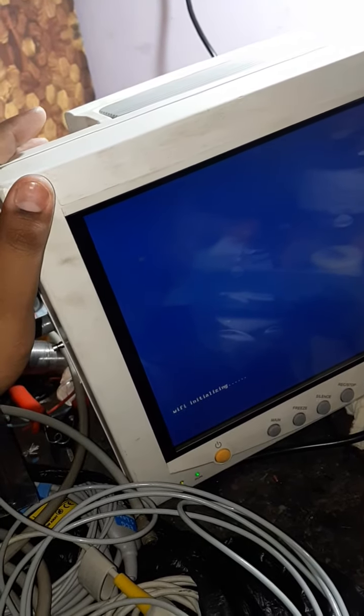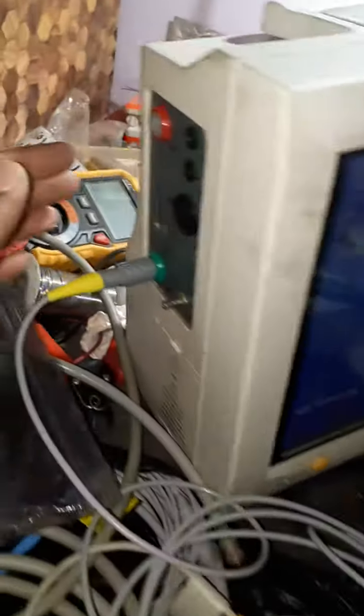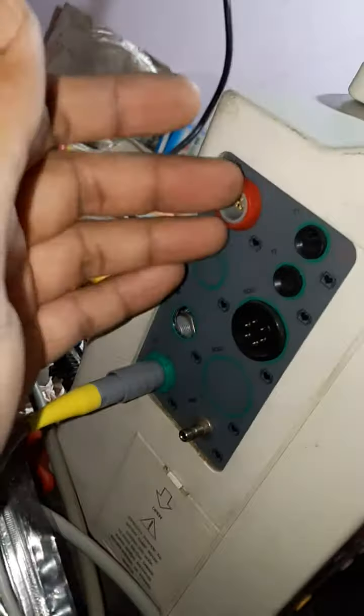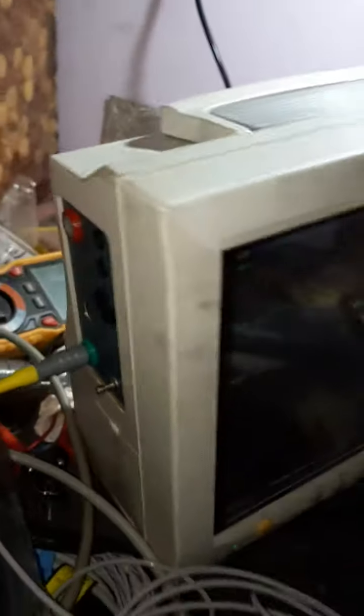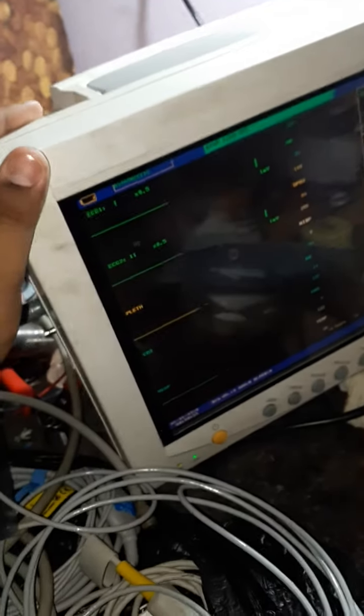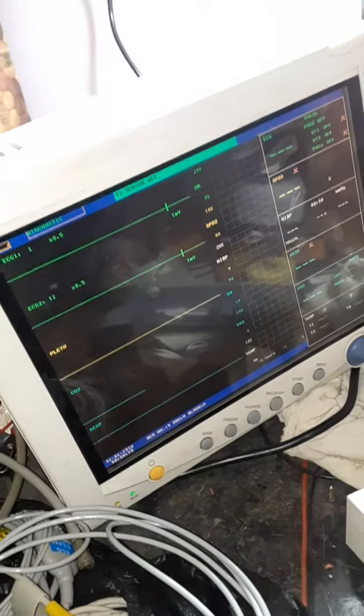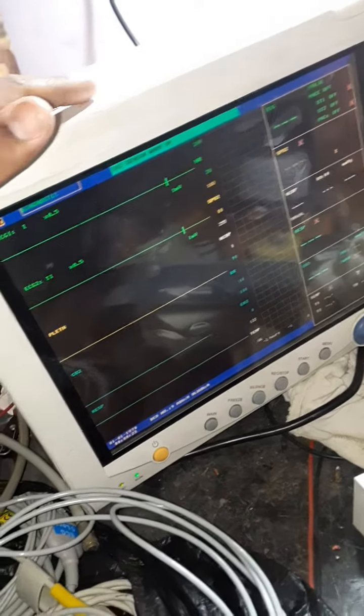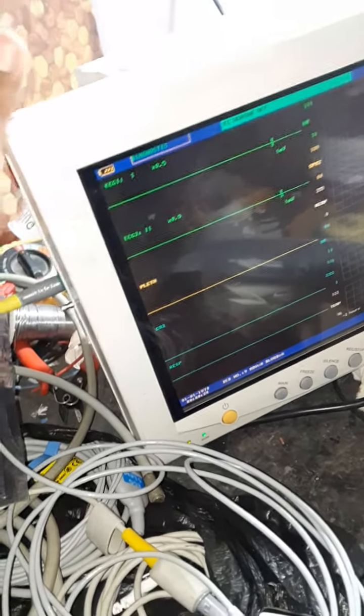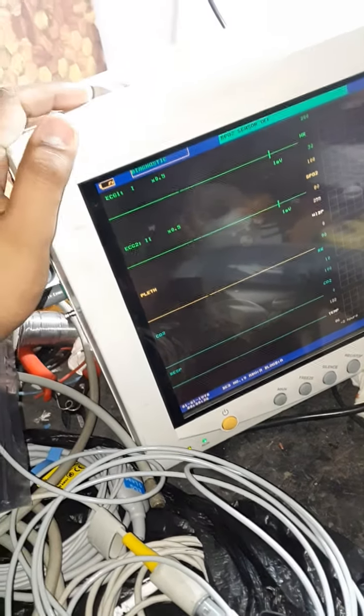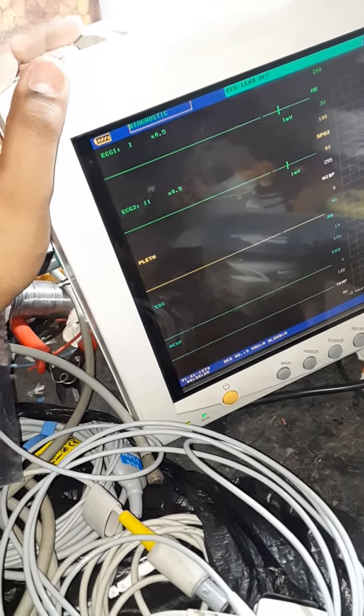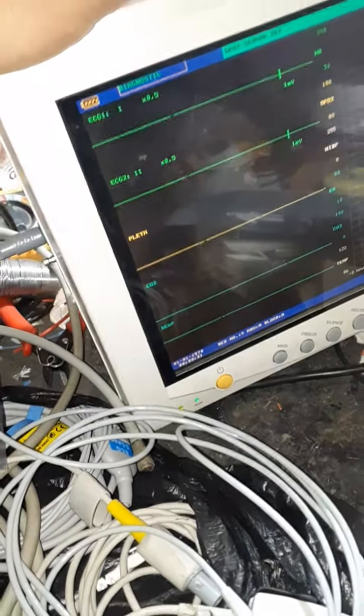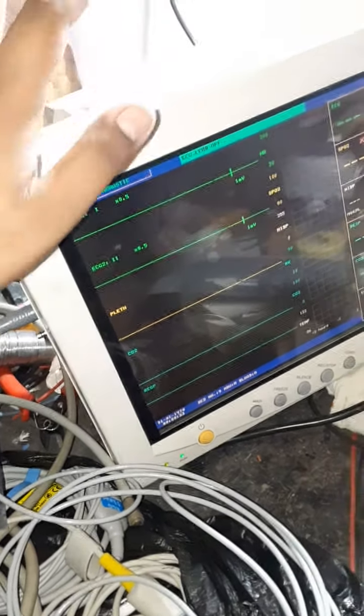The monitor is the same. Today I'm taking an old version of CMS 8000 which comes with 6-pin and 5-pin type modules. The new models come with different modules, but the remaining features are the same. New models have a single board inside, but in the last five years we've had multiple boards. This is a multiple board monitor, but the settings I'm showing work for both new and old models.